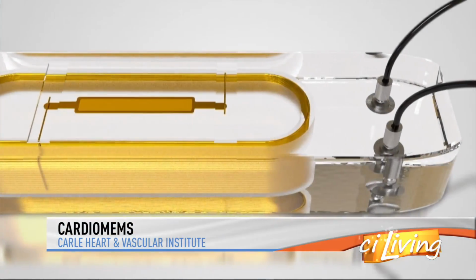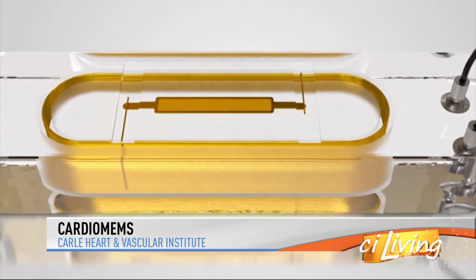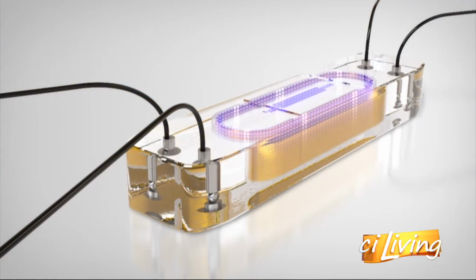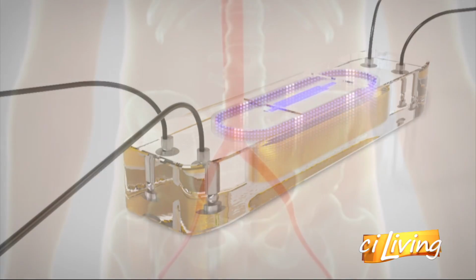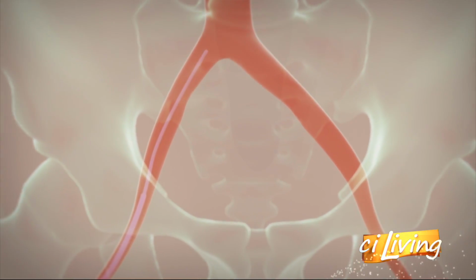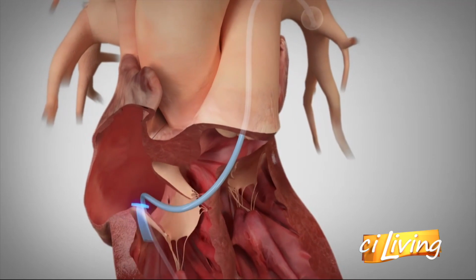So you've got this new procedure at Carle. Tell me a little bit about it and how it works. We have a new procedure called CardioMEMS. MEMS is an acronym for micro electromechanical system. It's a tiny little micro transmitter implanted into the artery of the lung called the pulmonary artery. So is that like an enlarged version of the transmitter that we were looking at? That is correct. And in this video, we can see how it is implanted.